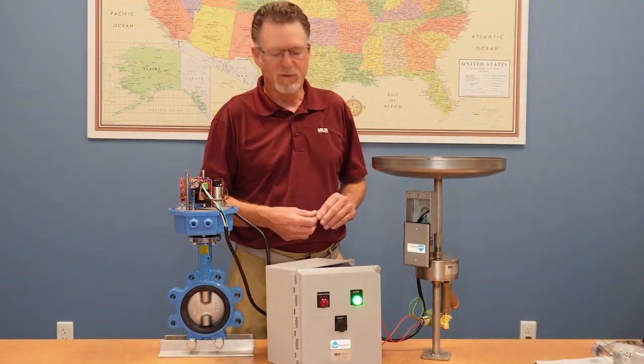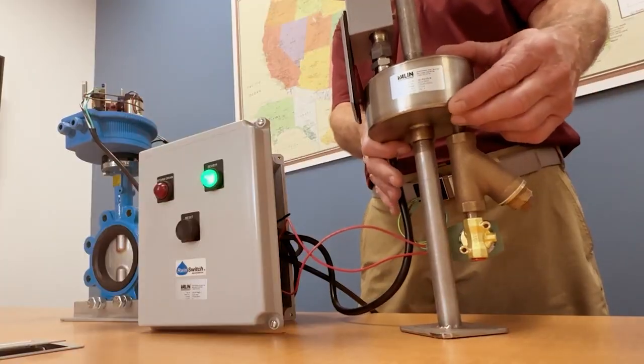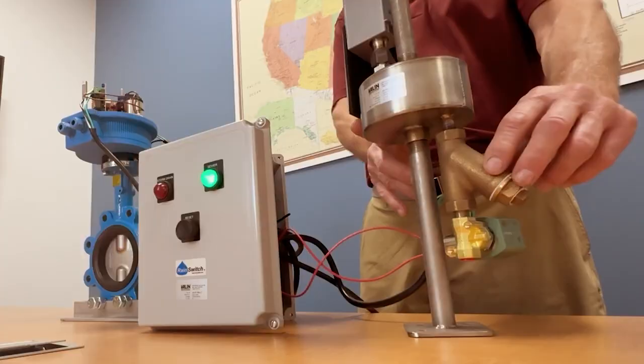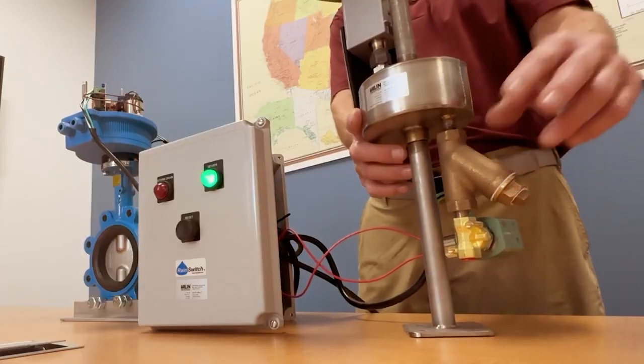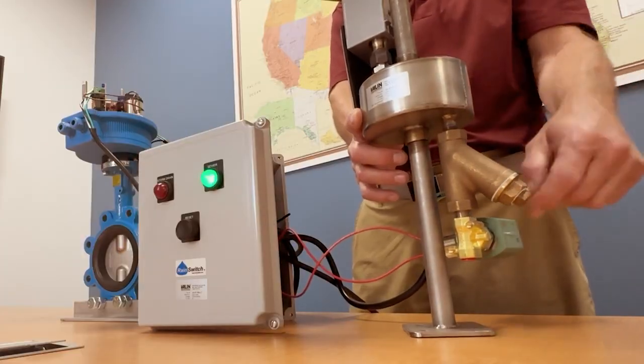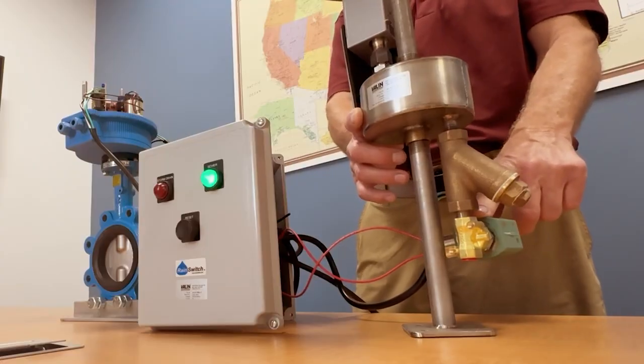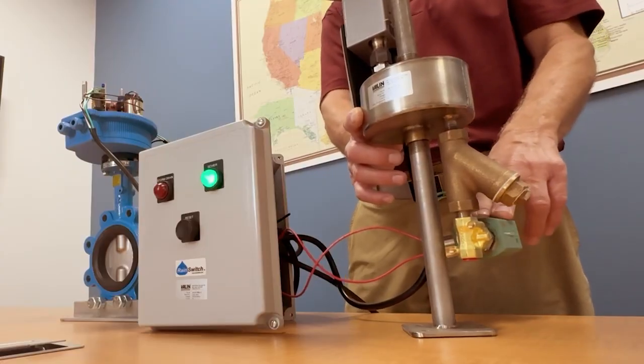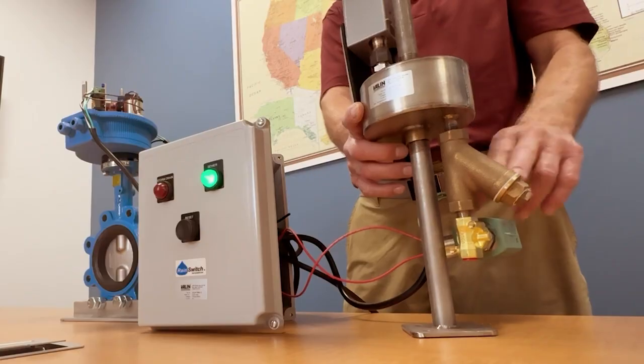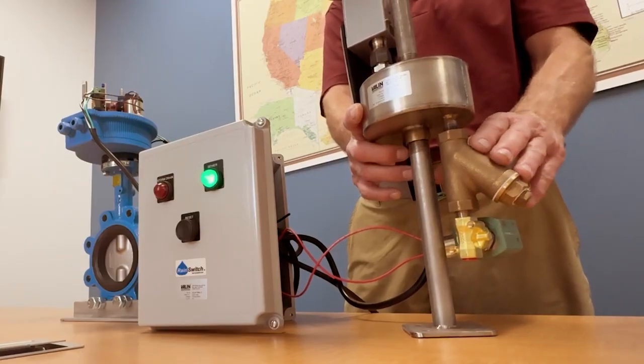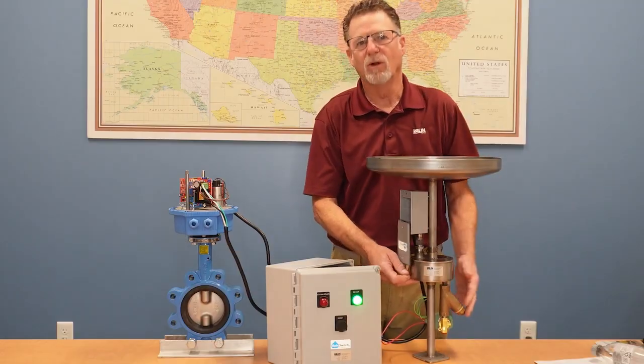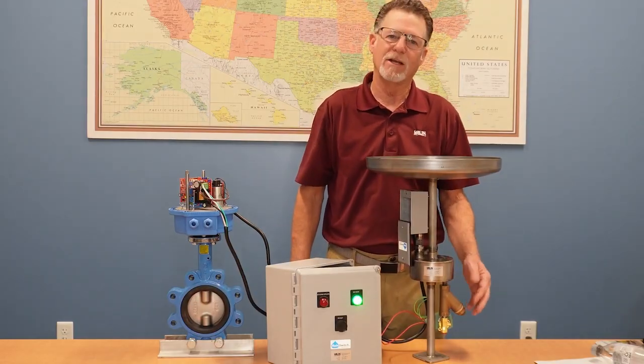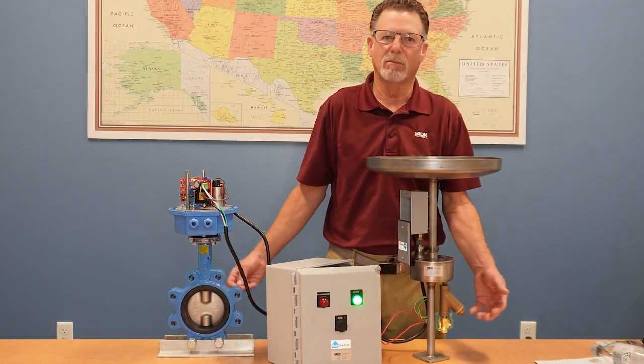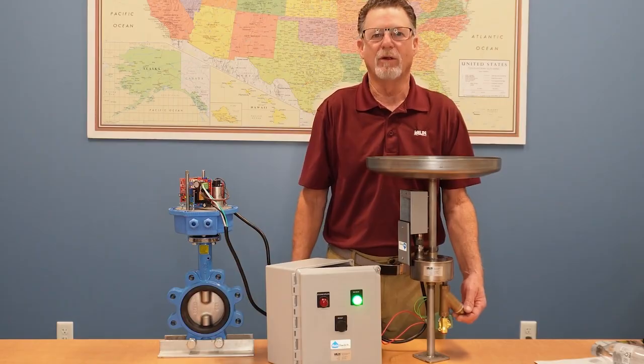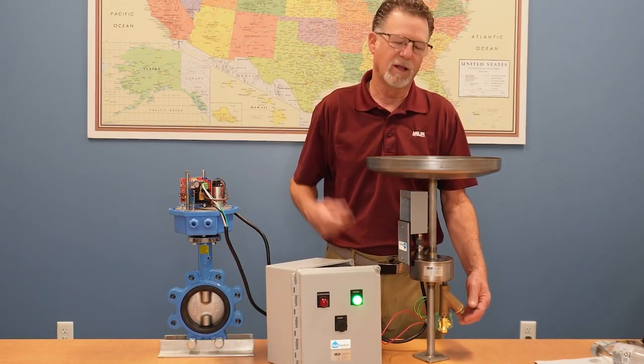It's a very simple device. This is the level chamber. We have a Y strainer here to keep any of the debris that gets in here from getting to the solenoid. The solenoid's got pretty small orifices in it, so we're just trying to strain anything out with the strainer here. You don't want it to plug up the solenoid valve, so that should be opened up and cleaned out probably annually. Depending where you're at, you might need to do it more often if a lot of debris is getting into it.